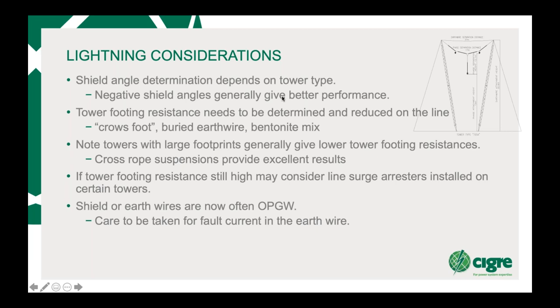You need to look at the tower footing, which needs to be determined to reduce resistance on the line. You can use crow's foot, buried earth wire, or a bentonite mix to reduce the footing resistance. And the thing about these large towers with very large footprints, with the guys, is that you get a very good earth mat generated, so you can get a very low resistance with these kinds of towers. Towers with large footprints give lower footing resistance, so the cross rope suspensions give you very good results. And if tower footing resistance is still high, you can use line surge arresters installed on certain towers.